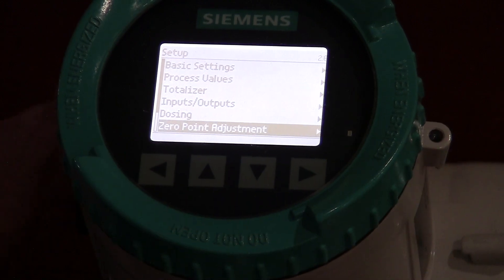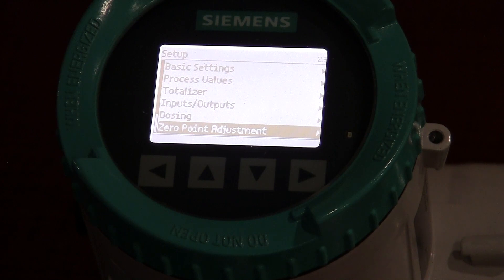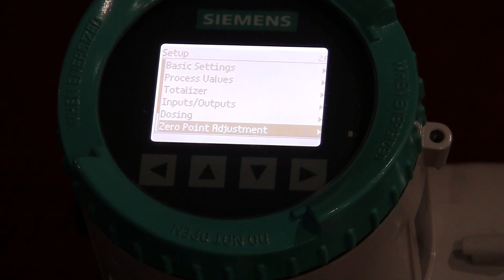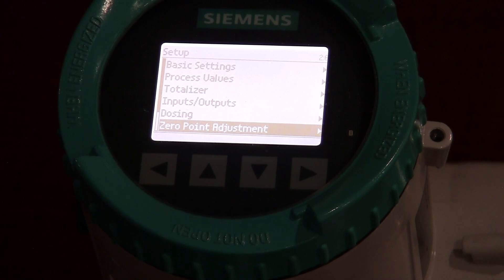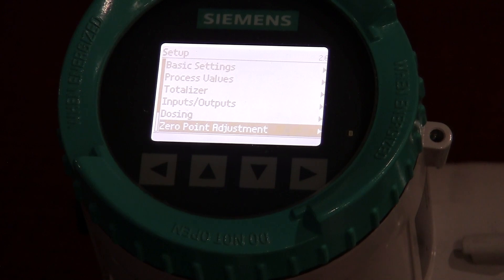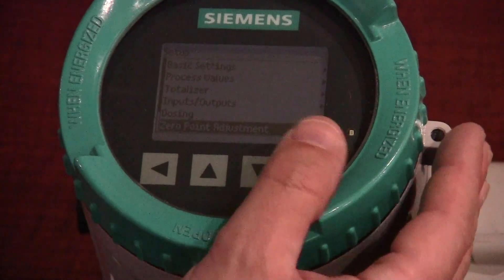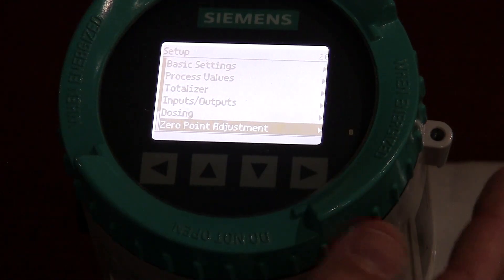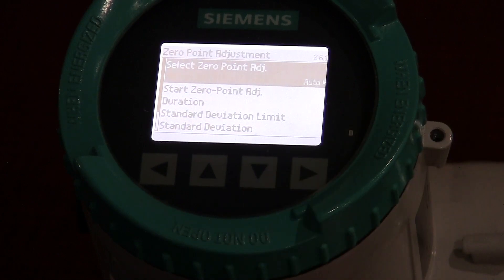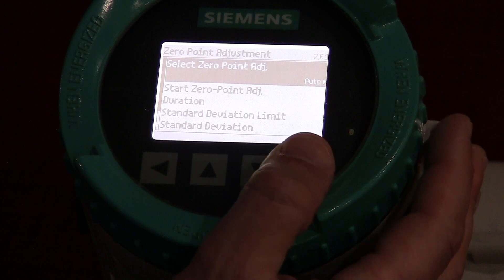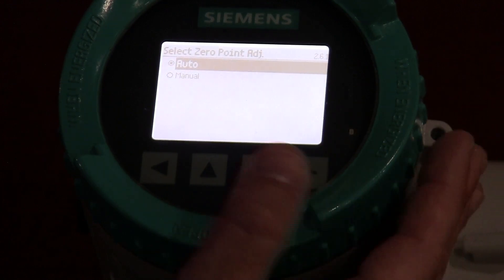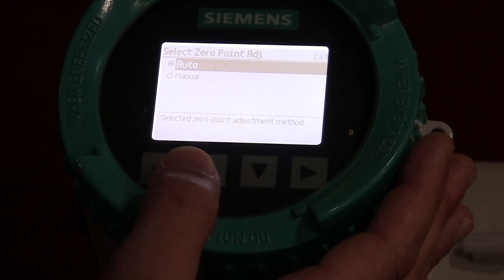One thing you want to look at is a zero point adjustment. This is suggested only for liquid applications. Essentially, you've filled the meter — typically you want to run it for about a half hour at your process temperature and typical process flow. You close your outlet valve, make sure the meter is completely full of liquid, and then close your inlet. So now you have a meter tube that's completely full with no flow moving — full of your process liquid, say vegetable oil for example. Then you tell it you're ready to do a zero point adjustment. I always have that set for auto, and what that will do is automatically make that correction for you.